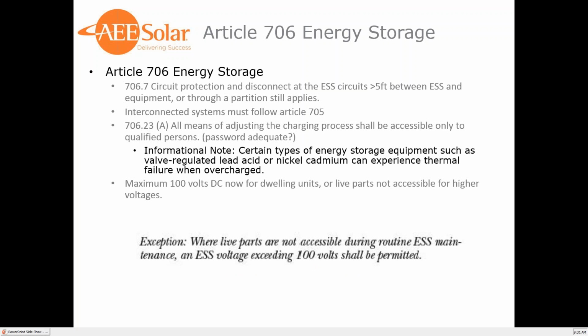Article 706, energy storage. 706.7, circuit protection and disconnect at the energy storage system for circuits greater than 5 feet between the energy storage system equipment or through a partition still applies. So this was still a requirement in the 2014 code, but it is saying if your energy storage system is greater than 5 feet from the next device, you must have circuit protection and disconnecting means, which could be essentially the same thing. It could be a circuit breaker that you could use as a disconnect. This could definitely get challenging if you have a large system with multiple battery banks or stacked inverters, where you have multiple parallel cables. Having a disconnect that is able to switch that much current could be a challenge.